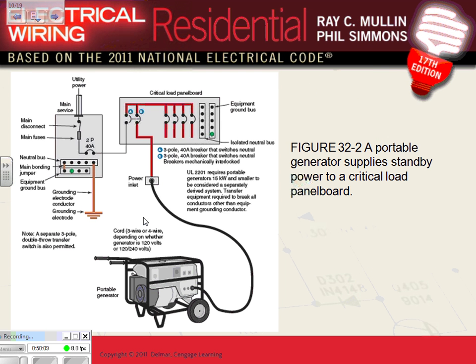Look at the next. This is the same picture that you guys are looking at. Now, if I lose the power, so power is gone from here, look what happened. The first thing you need to do is go to that little switch here and flip the switch, right? So now the switch was on the utility. I lost utility. I'm going to go physically, mechanically, and turn this three-pole switch, three-pole right here. If you look, here's a three-pole and three-pole tied together. One of them is up. I'm going to switch that one to the generator, it is up now.